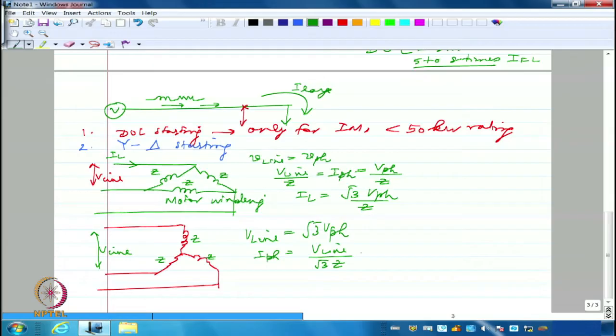So if I try to look at the ratio of I line delta and I line star, I can say I line delta is equal to 3 times I line star. Right? So I'm going to have 3 times. So by doing this, I'm essentially reducing the starting current, no doubt. But what happens to the starting torque? That also we'll have to check. We said that the torque is proportional to current square, right? You remember we wrote it like this, I2 square R2 dash by S omega S times 3. This is what we wrote as electromagnetic torque.